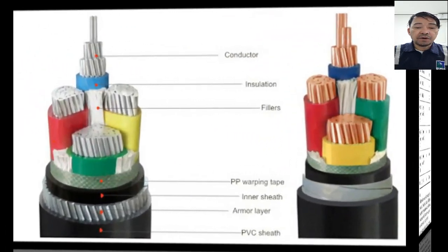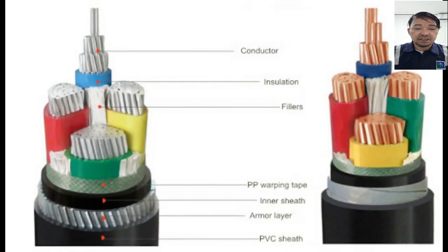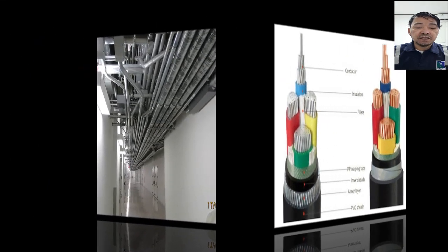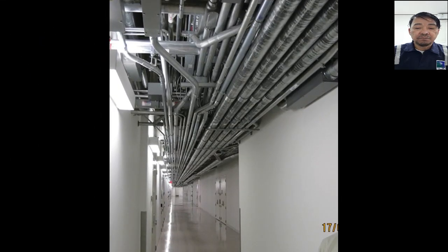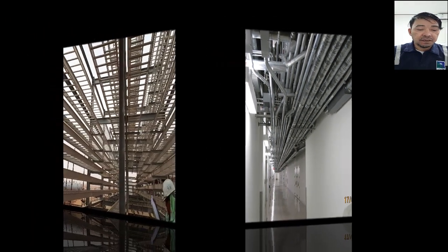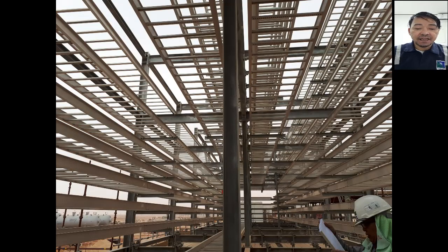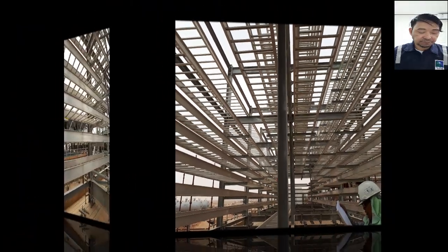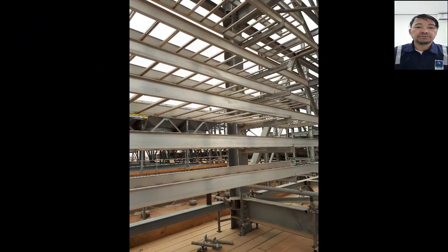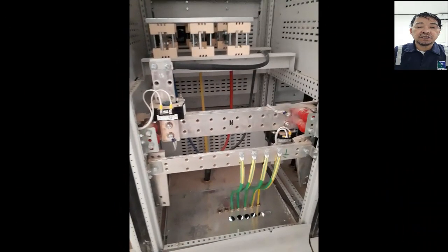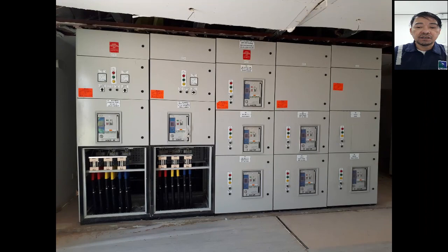Shields and armor of power cable shall be grounded at both ends. Metallic conduit shall be grounded at both end points by bonding to a grounding conductor, a grounded metal enclosure, or to a grounded metal cable tray. Metallic cable trays shall be bonded to the local ground grid or ground electrode at both end points. Ground buses in switchgear, switchboards, and motor control centers shall have two connections to the local ground grid or the main ground electrode.